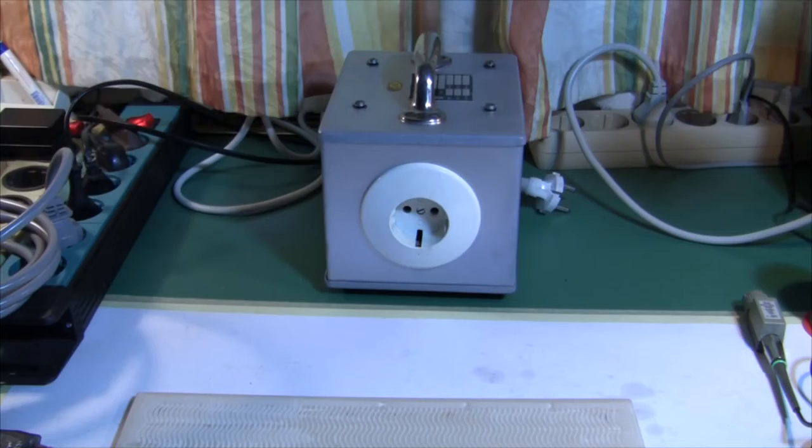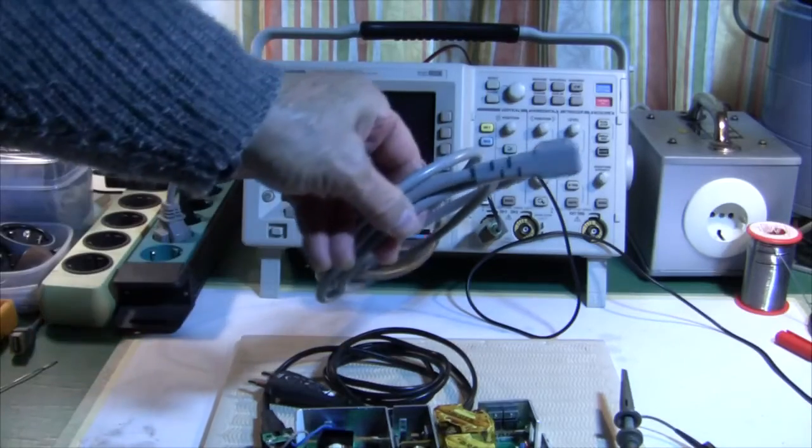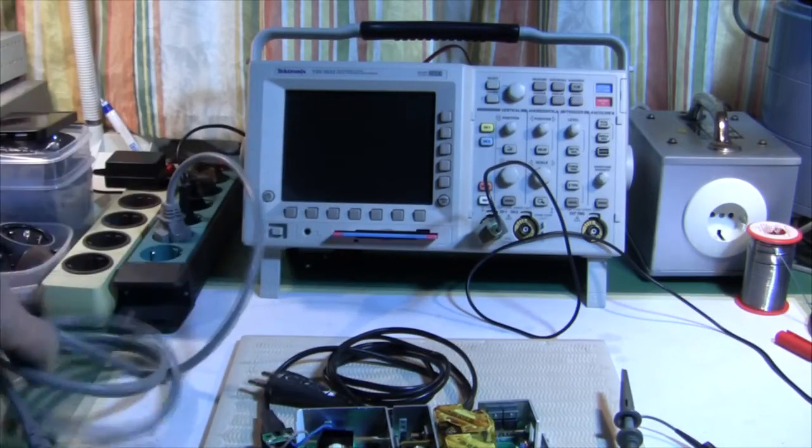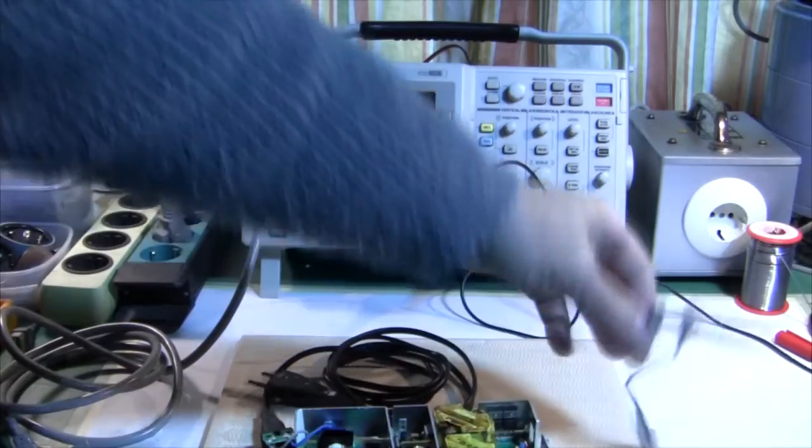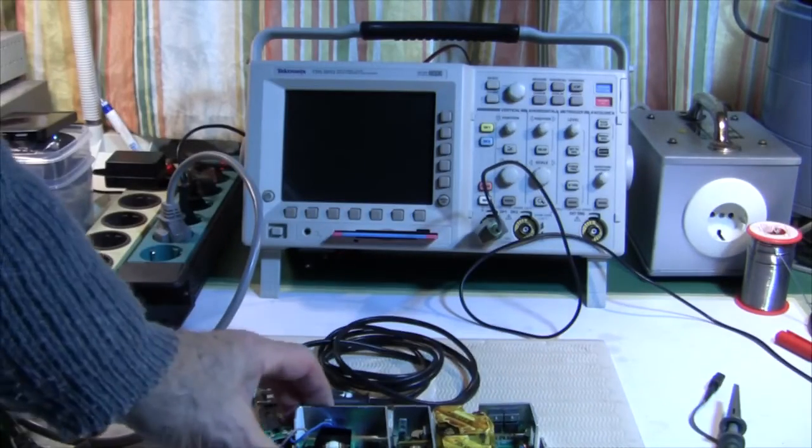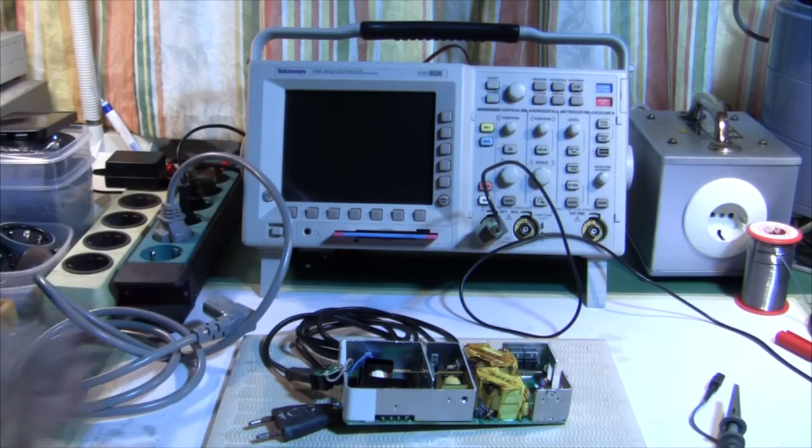The next thing you need is an isolation transformer. Our oscilloscope is connected to protective ground via the mains cable. The ground is on the ground clip of the probe. High voltage is on the parts of the power supply. So we have to break this loop somehow.